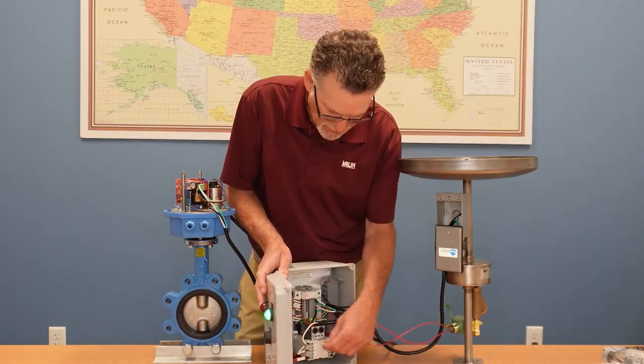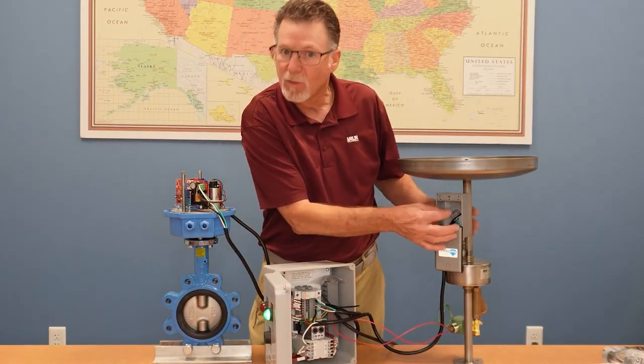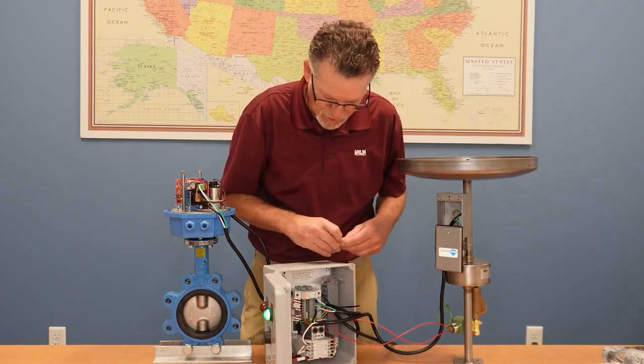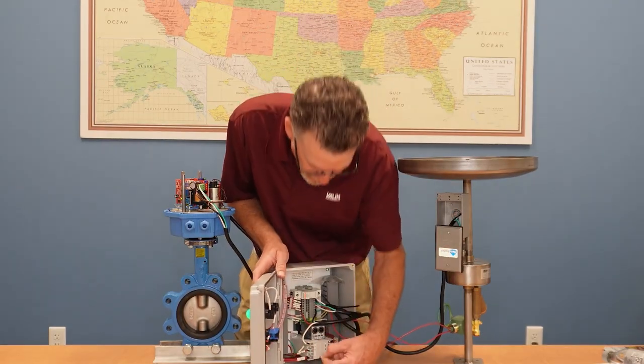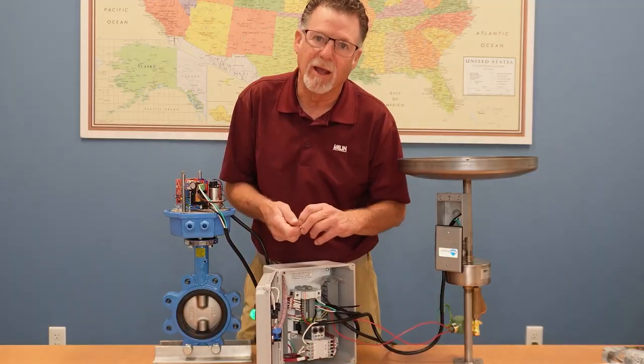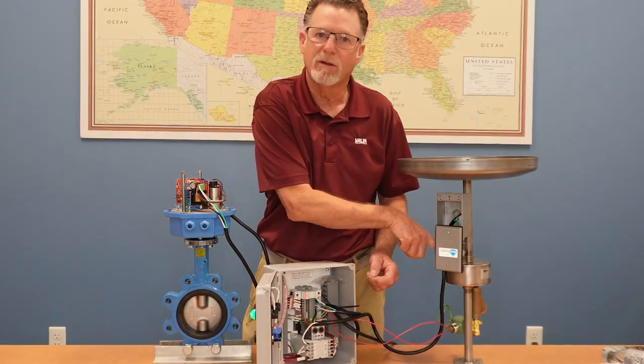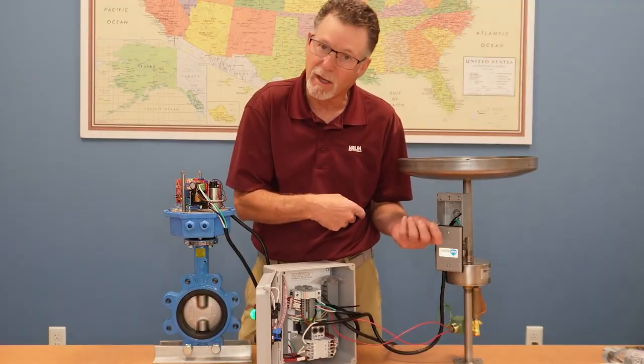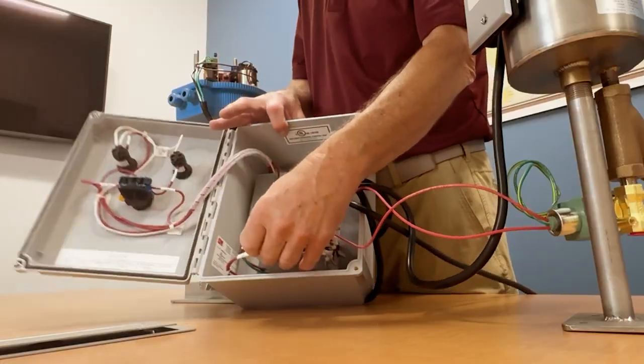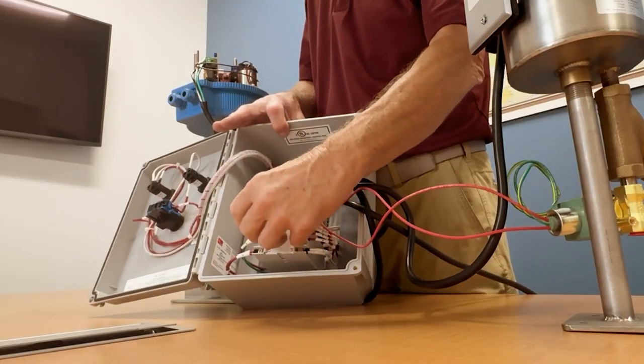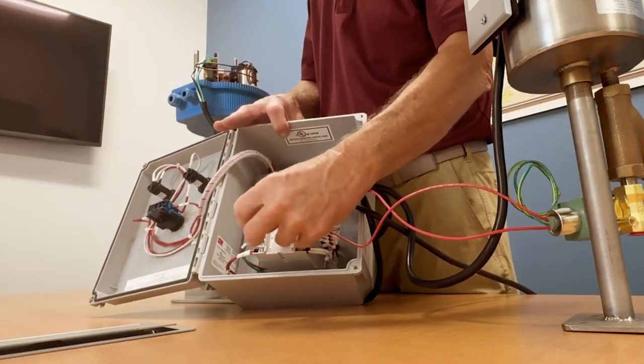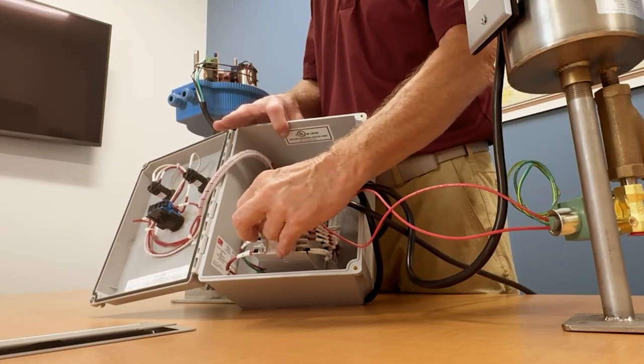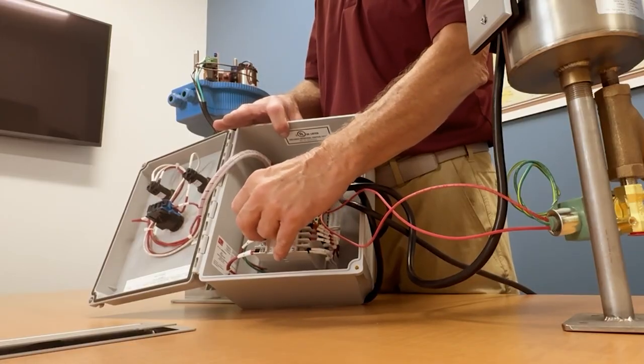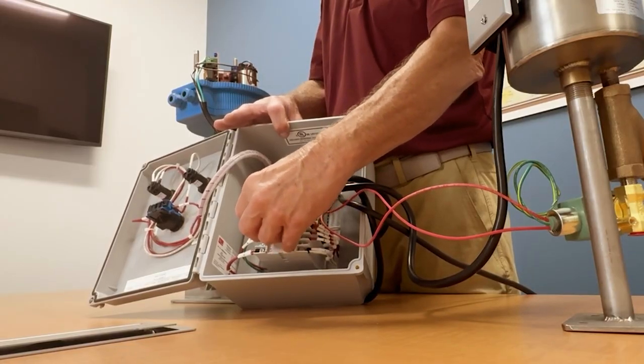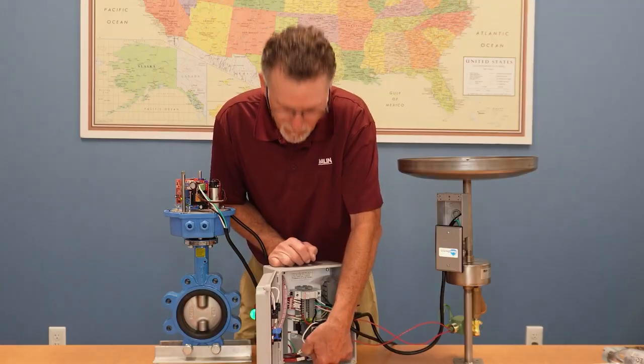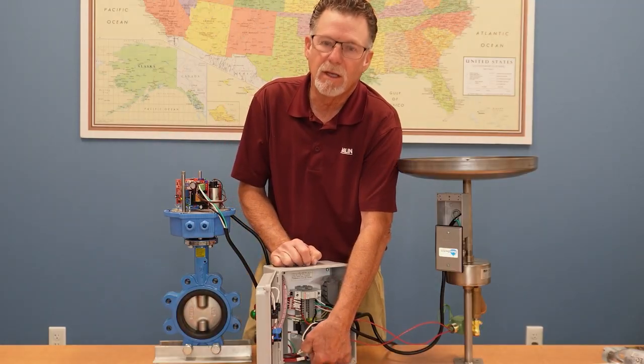Again, at the pilot station, you can either check it here, which may not be convenient. You can also jumper between the H and the G on the relay, which is the same as putting water in the RainSwitch or doing the jumper like I did here. The same thing occurs here, just by jumping the H to the G, H to ground. We're doing the exact same thing as I just did over on the RainSwitch. So hold it for 3 seconds. 1, 2, 3.